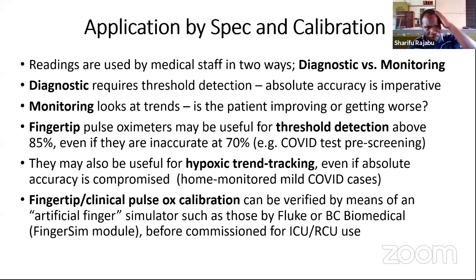But what we need to think about also, these pulse oximeters, although they are calibrated by the manufacturer, they need to be verified to see if they're still working within the required conditions, so that we can determine which one is accurate and which one is not accurate. How do we know that? So we have to use those vital sign simulators. Even those vital sign simulators, we need to understand how they operate. For example, on my side, I was using a BC Biomedical finger simulator.